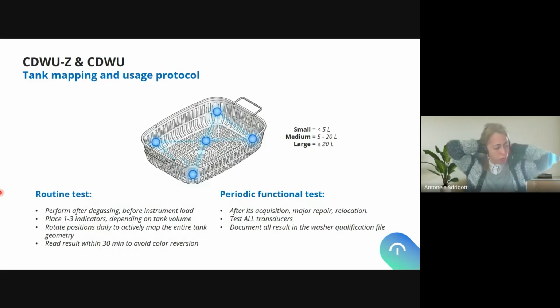As I have mentioned, we can use the indicator both for routine tests as well as for periodic functional tests. Of course, the number of indicators we use will be related to the size of the ultrasonic washer. The bigger the ultrasonic washer, the more indicators we will use, because we need to corroborate the performance of every transducer during the periodic functional test. So we can use this indicator not only to make sure that on a daily basis we are delivering the right cavitation energy, but also, during the periodic functional test, to map the tank and know the cold and hot spots of cavitation that my ultrasonic washer delivers in its full volume.